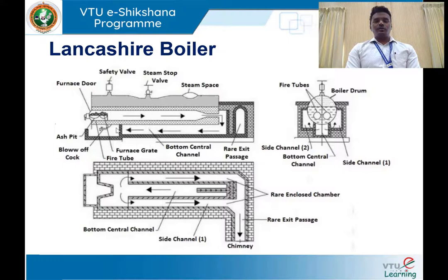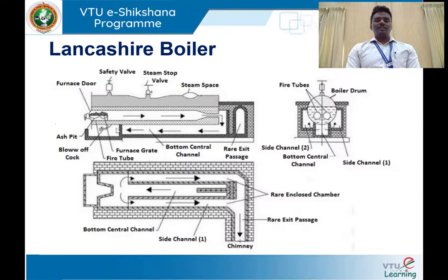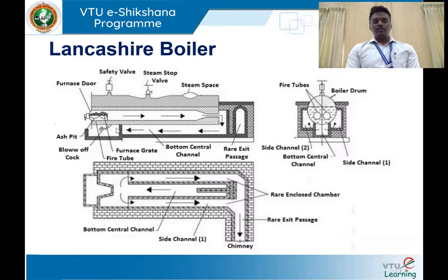The Lancashire boiler basically consists of a boiler shell and two flue tubes. The furnace is placed at one end of the boiler shell — the furnace is a part of the boiler shell. Coal is used as fuel. Once the coal starts burning, it releases hot gases, which are made to pass through the fire tubes from one end to another. The fire tube changes its cross-section nearer to the rear end of the boiler shell to increase the velocity of the hot gases.